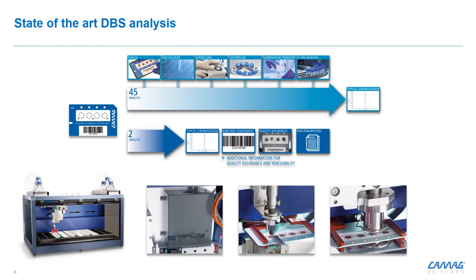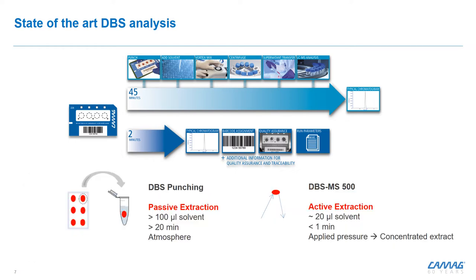We can load up to 500 DBS cards into the instrumentation, which are then handled in a fully automated fashion. The main difference between punching and this direct elution is that we have active extraction — always fresh solvent hitting the sample — and we end up with only about 20 microliters of a very concentrated extract within less than a minute per sample.